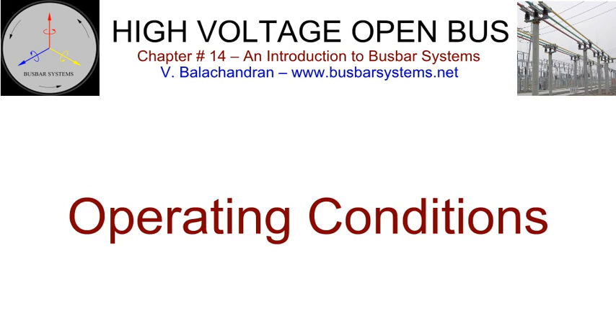The impact of these increases with the increase in the rated voltage of the switchyard. The ground clearance, phase spacing, and the height of the conductor from the ground increase with the increase in the rated voltage. These need to be understood while sizing the conductor and the supporting arrangements. The ampacity is significantly impacted not only due to variations in the ambient temperature but also due to wind and solar radiation.